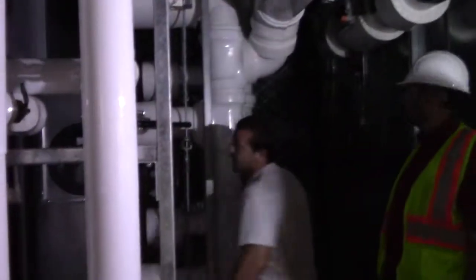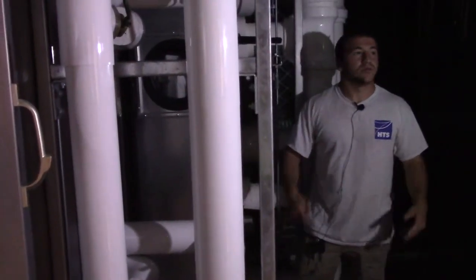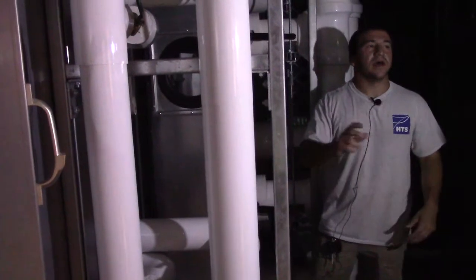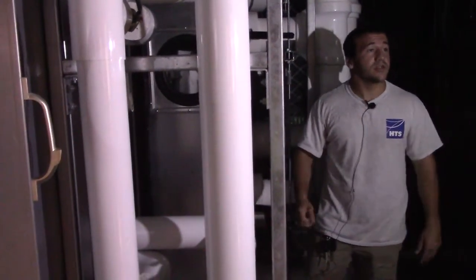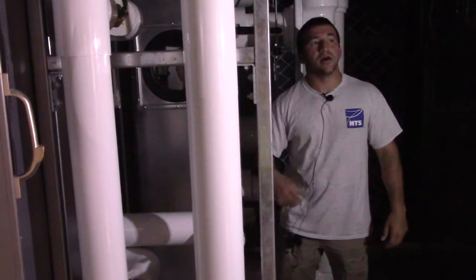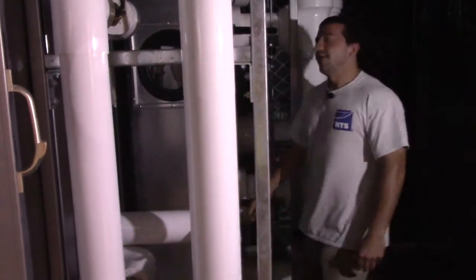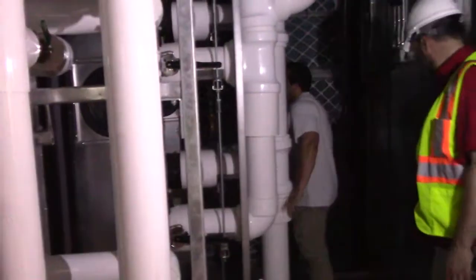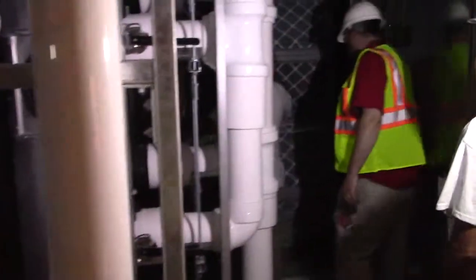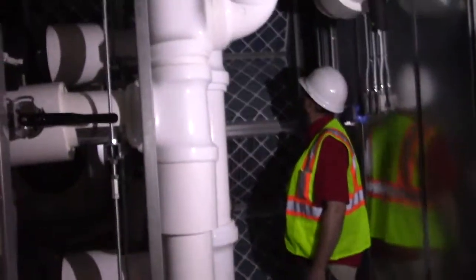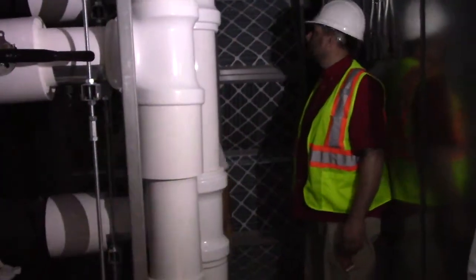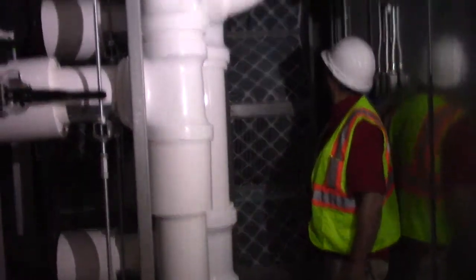And then you've got your hot water coil here and chilled water coil here. If you ever have to clean the coils, they don't want any sort of chemicals on them. What we use and recommend is Dawn dishwashing detergent. Just mix it in a pump sprayer, spray it on, and then rinse it off. And then you've got more filters here. Change the filters as needed. I think that's about it in this section. Do you want to take it to the next one?